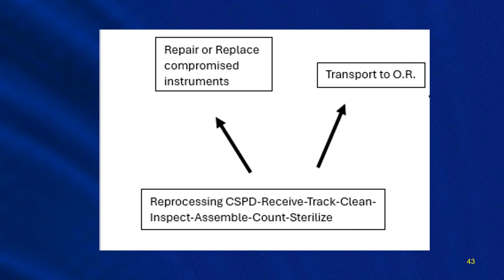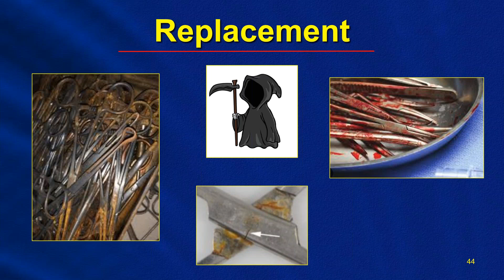So Central Sterile technicians on the front line face enormous challenges in monitoring the high volume of instruments they see and checking for blemishes, for corrosion, for anything that could impact patient safety. So how do you really know when an instrument is at its end of life? Well, indicators would be things such as rust on instruments that cannot be resolved, decreased functionality, corrosion of instruments, permanent stains that cannot be removed by stain removers, cracks in instruments, and basically instruments that have outlived their useful life. They're no longer under guarantee or warranty, and basically instruments that can no longer safely be used in surgery.